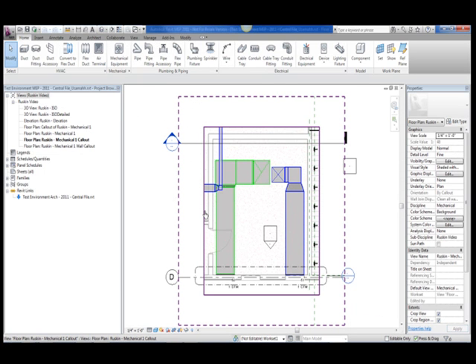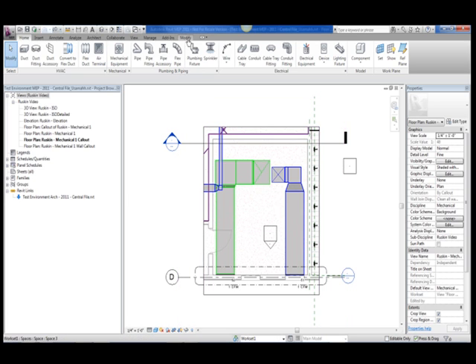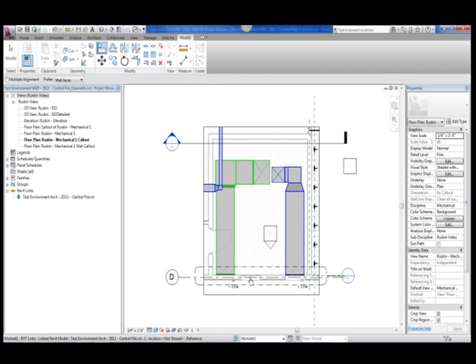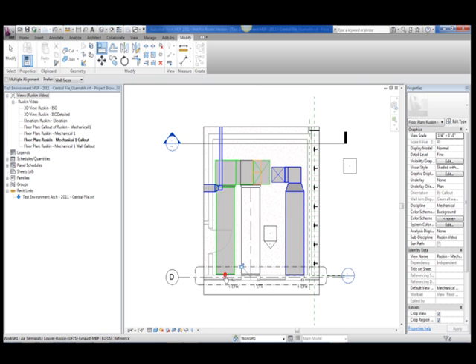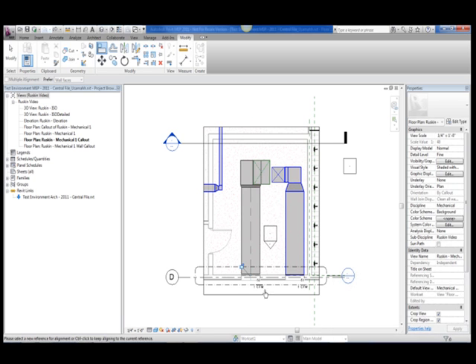After receiving notification from the architect that there have been modifications to their model and updating the architectural model link in my mechanical project, I get an error that tells me that constraints have been removed. The warning is letting me know that some of the changes that were made in the architectural model have caused some objects in my MEP model to remove their constraints. In this case, there are only louvers that are constrained to the architectural model so I know to check their constraints.